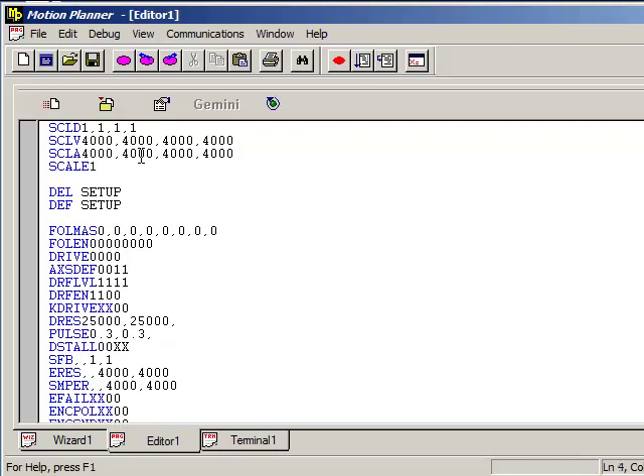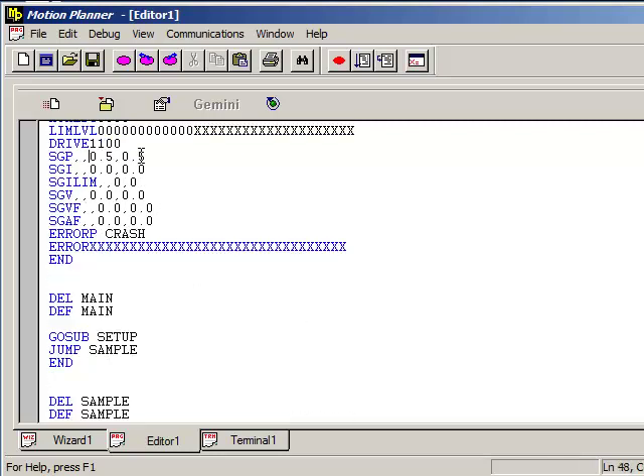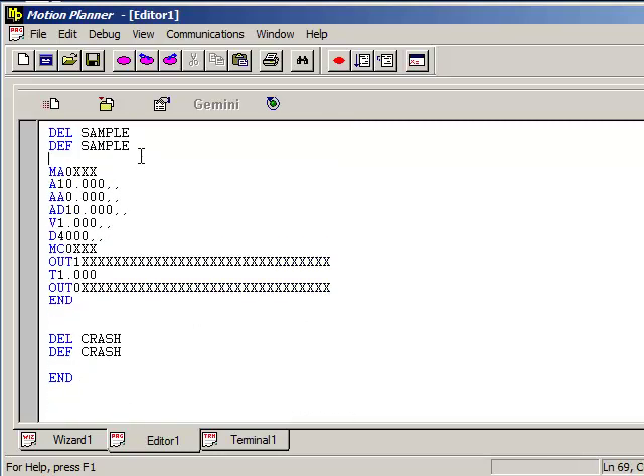These you can set in the terminal window on a new 6K by typing them into the terminal window. So because these are set before the first delete and define, it's just like you're typing them into the terminal window, but when you do a save, it'll be stored within the program. Then go to the very bottom, type STARTP MAIN.